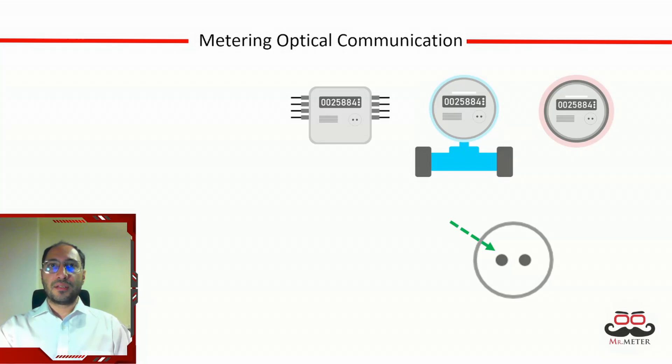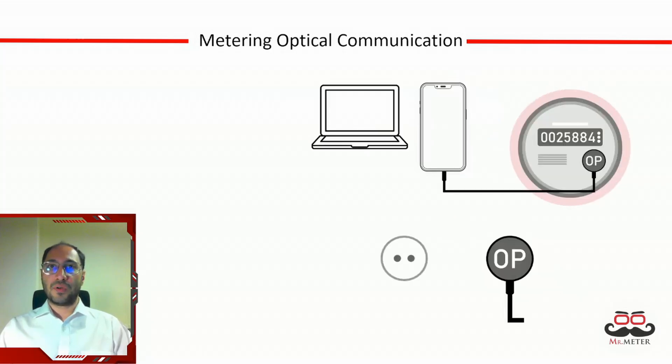One LED typically acts as a light emitter sending signals to the external device, while the other one acts as a receiver collecting signals from the external device. This bi-directional communication is essential for tasks like reading meter data, configuring the meter, or updating its firmware. The use of these two LEDs facilitates a form of serial communication based on IEC 62056-21 standards.